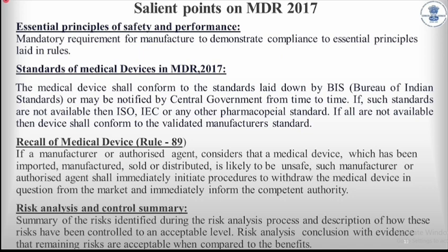concerned about is the standards which are applied to medical devices. As per the regulation in India 2017, all medical devices have to conform with the standards laid out by the Bureau of Indian Standards. In the absence of that, they may refer to or adopt an ISO standard, IEC standard or pharmacopoeial standard, which is available for the kind of medical device.